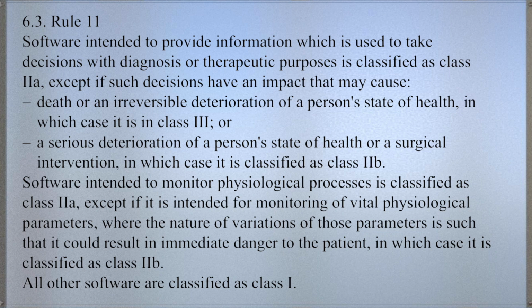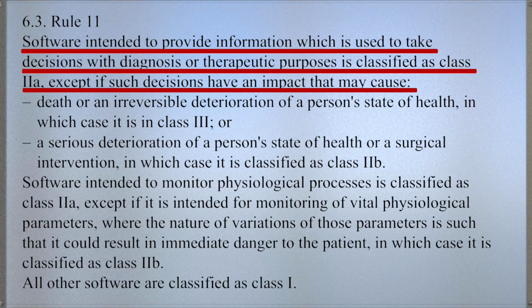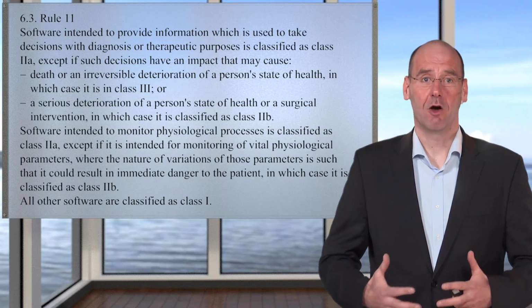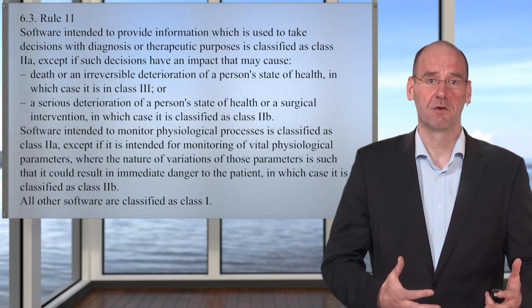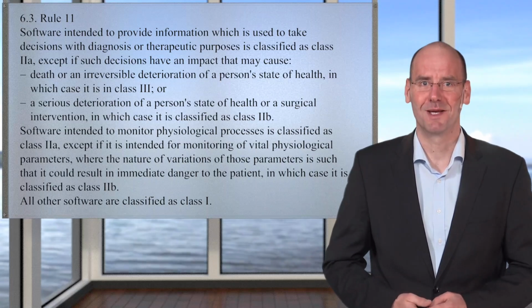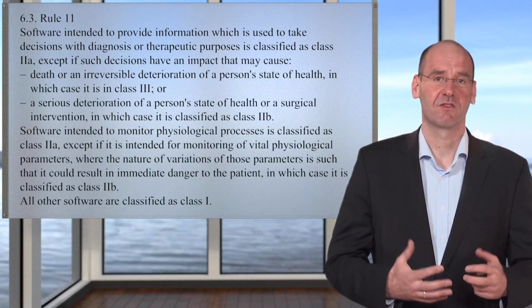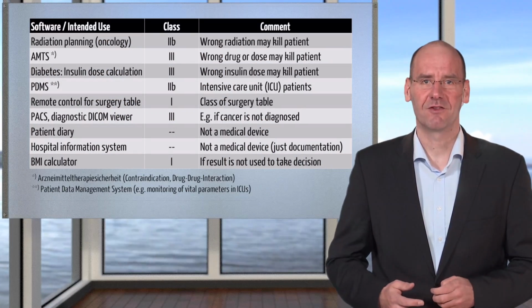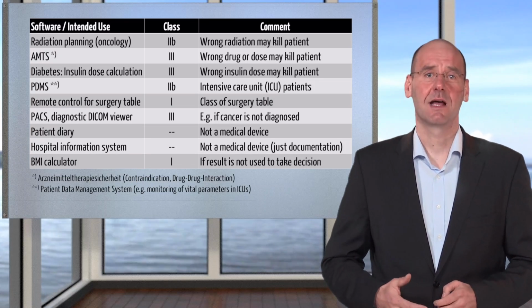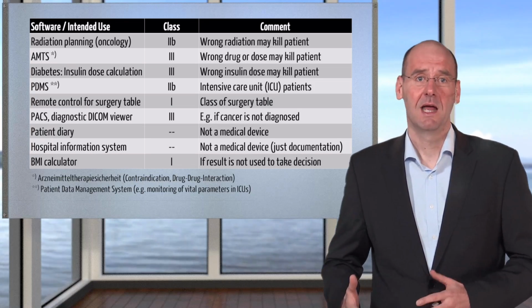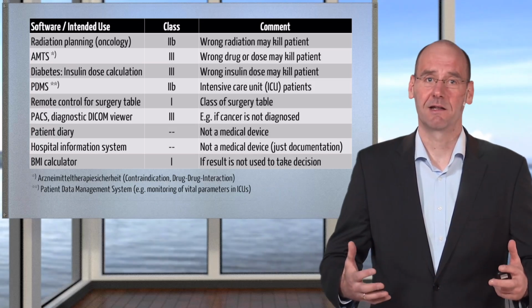As you can read, quote, software intended to provide information which is used to take decisions with diagnosis or therapeutic purposes is classified as Class 2A or even higher. As medical software nearly in all cases serves the purpose of diagnosis and therapy, otherwise it wouldn't be a medical device, kind of no Class 1 software is left. A drug management system, in the past Class 1, is now Class 2B or even Class 3. A patient data management system, at least Class 2B.